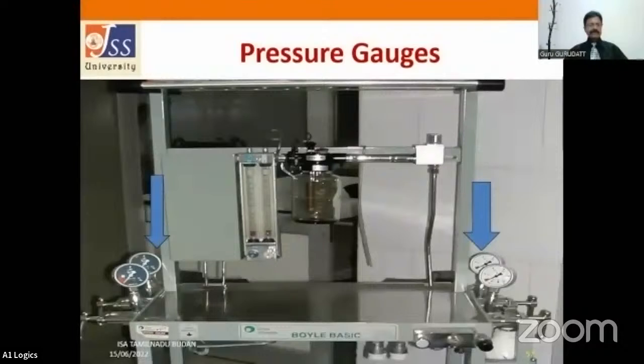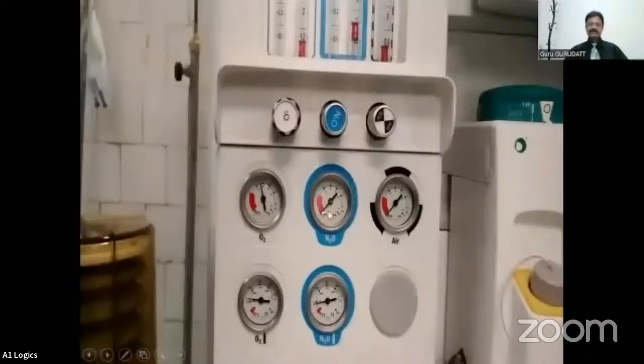Now, I told you these pressure gauges are also present over the yoke assembly in the older machines. They are connected to the yoke assembly itself. But in the modern workstations, these pressure gauges are present just below the flow control knobs. Another very important safety feature adopted in the modern workstations regarding the pressure gauges is that in the older machines, the pressure gauges were present only for the cylinders. Now the pressure gauges are also there for the pipeline system.